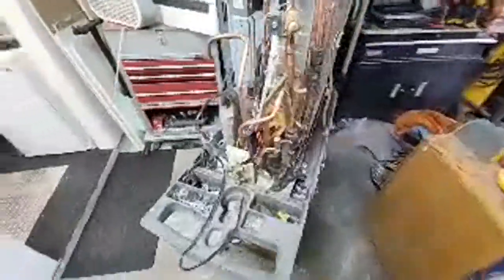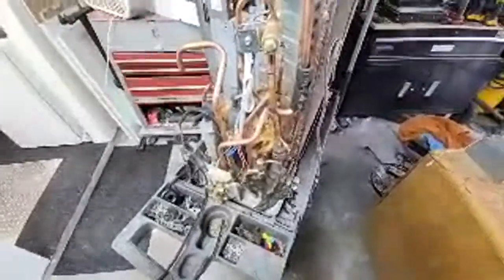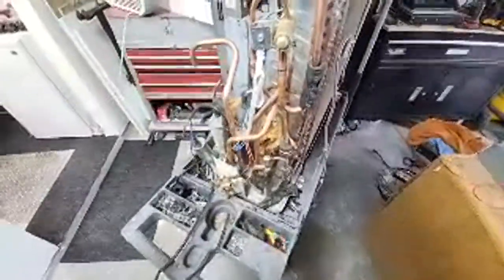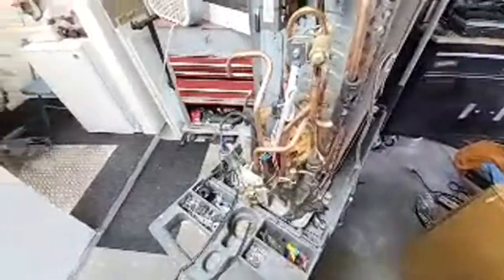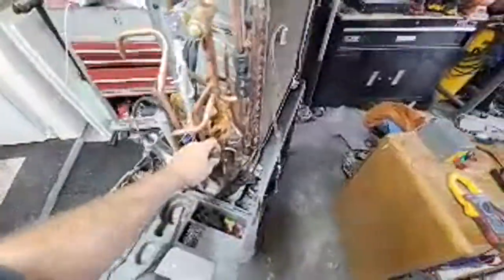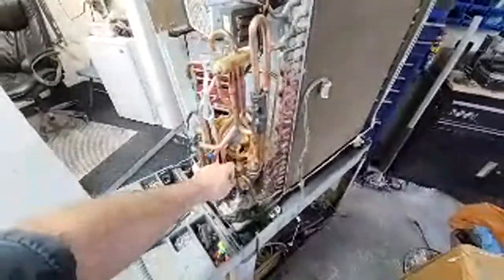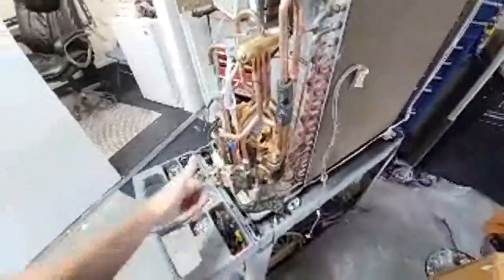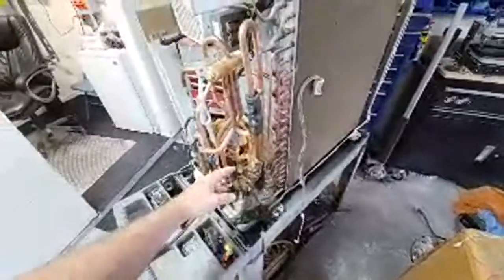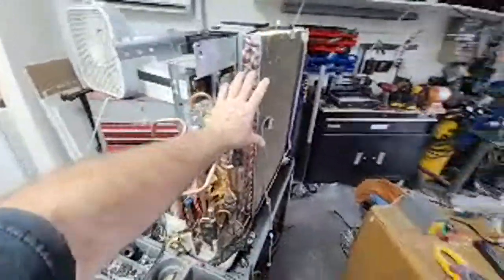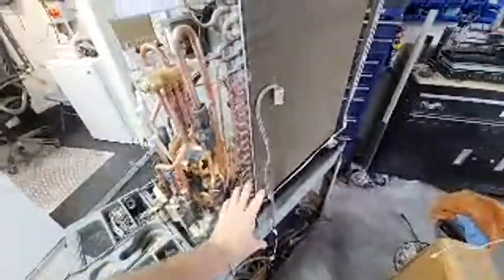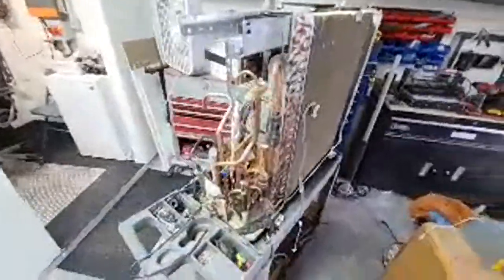So it'll freeze me out in that room, taking the heat out of that room when I want to use the room. So I'm going to want to turn off the cooling in that room and just let the computer and stuff heat me up in there. So it'll wind down this one, and I put it in the other mode, and then it'll basically switch from summer to winter mode, and I'm going to have my microprocessor start modulating the other one, which is going to be this top half of the coil, I think. Or I might use the bottom half. Maybe that'd be better. No, top half. The water can run down on the condenser.